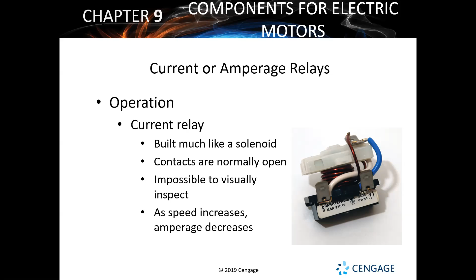So again, operation of a current relay is much like a solenoid, which you can see right here. We've got this electric coil. You've got power coming in, power going out, and when that power runs through there, it's going to pick up a little bit of it. It's going to see, okay, how much amperage are we having through here? And that amperage and that electricity will build up and will disconnect and not allow power to pass through to the start winding after a certain amount of time, or once it gets to a certain amperage. That's the whole idea behind it. So speed increases, amperage decreases, and the start winding is able to be disconnected from everything. And then you'll just have the run winding going. So that's the whole idea behind these, really.